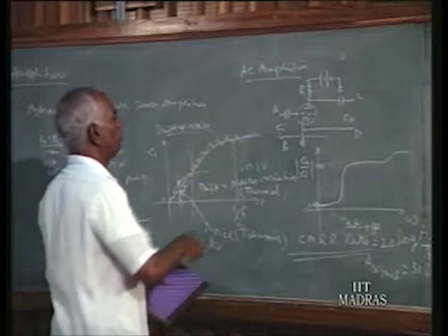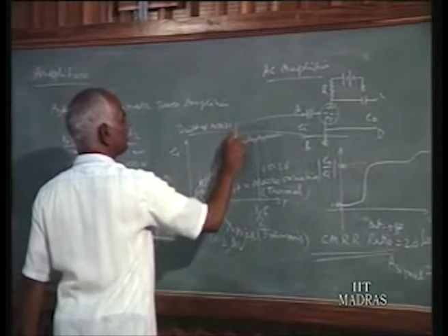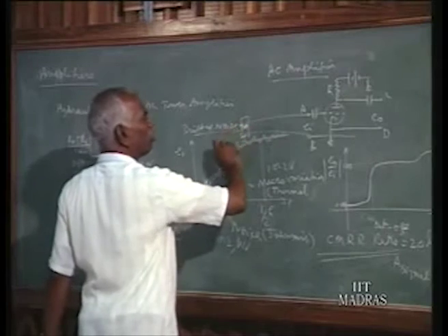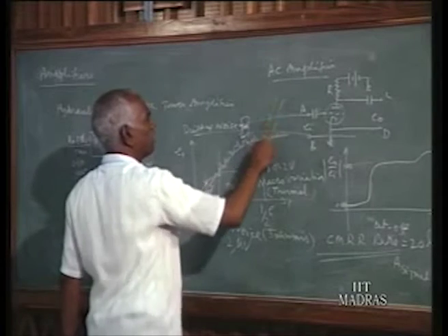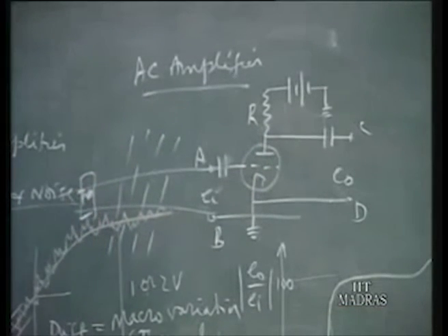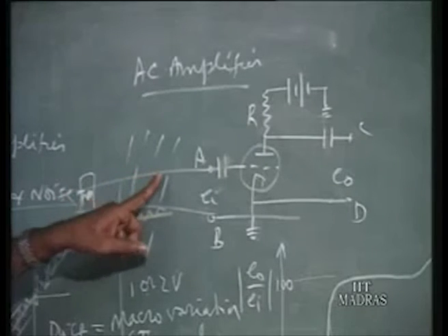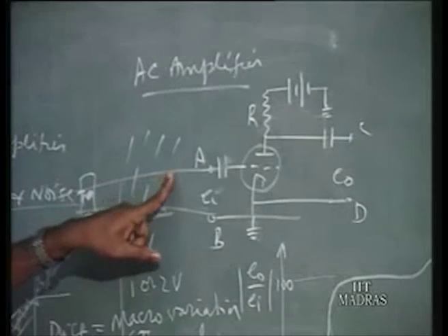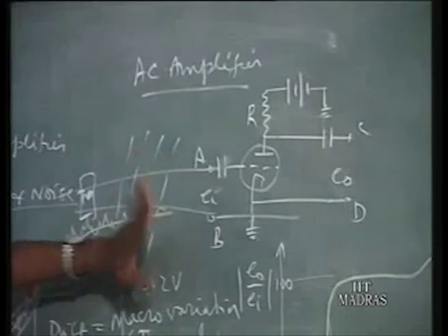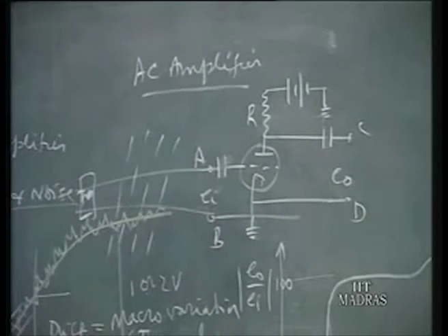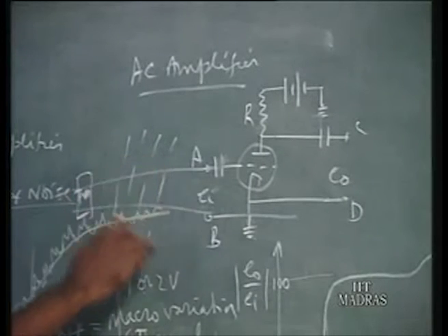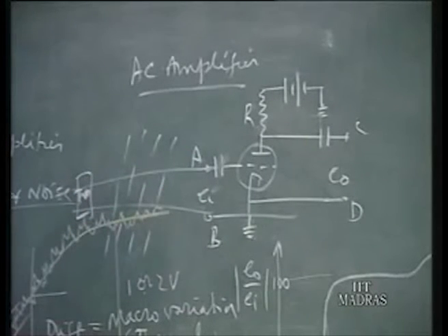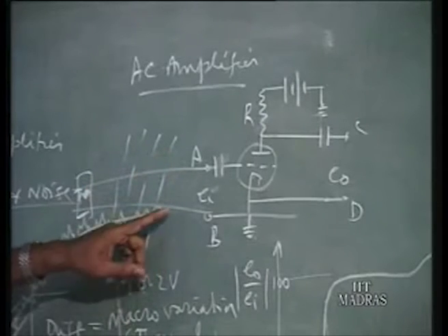That matters when you connect a wire to a transducer at a long distance from the amplifier. Any nearby power line will produce some voltages on the wire carrying the signal. Such a superimposed signal can be eliminated by having another circuit, as given in standard books. By having another circuit, this erroneous voltage is allowed to drive current in two opposite directions, and only the differential is allowed here.